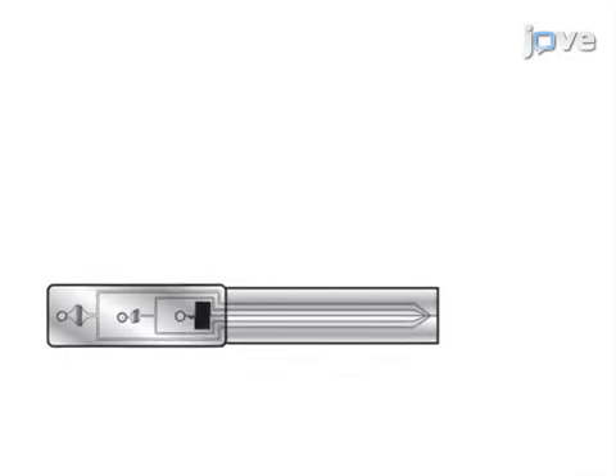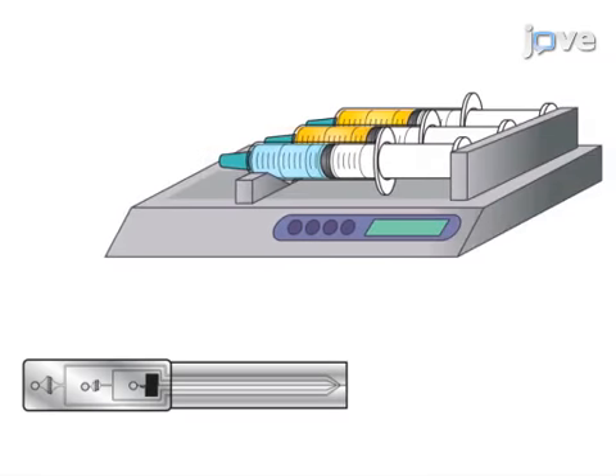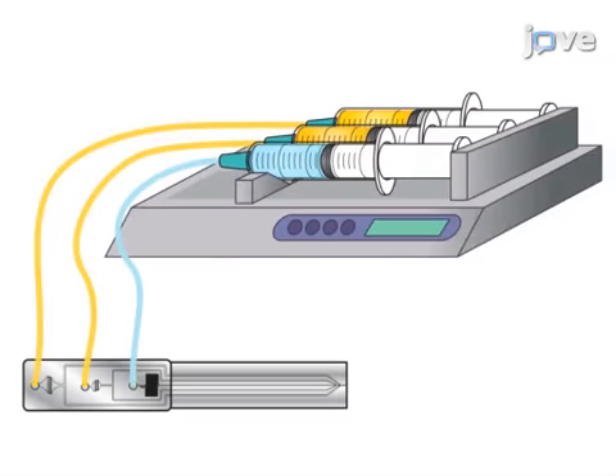The second step is to connect syringe pumps to the microfluidic chip. The pumps will supply the aqueous sample and the highly volatile and immiscible organic carrier phase, PFH. When the syringe pump is turned on, the microfluidic chip generates monodispersed droplets of the aqueous sample solution or a cell suspension by flow focusing with PFH and ejects these droplets with additional PFH from the chip as a liquid jet.